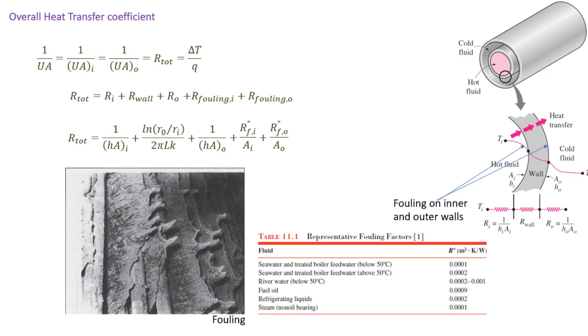Keep in mind that although you can find representative fouling factors, they will vary depending not only on the operating temperature and the fluid velocity, but with how long the unit has been in service. A new heat exchanger has a fouling factor of zero. As time increases, that fouling factor increases.